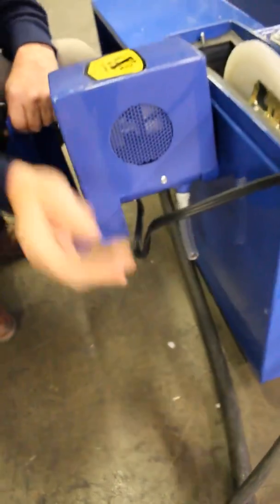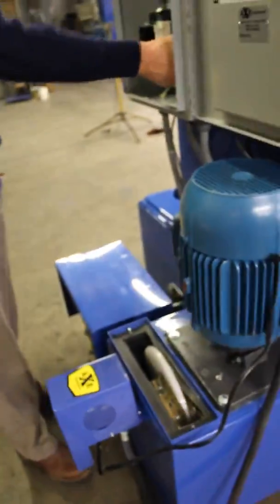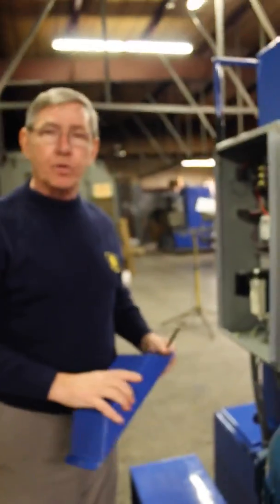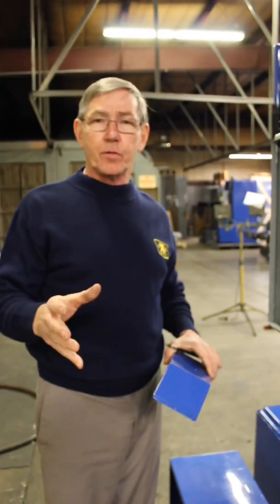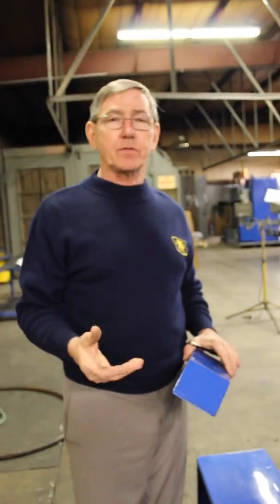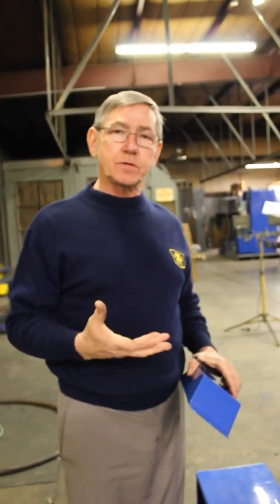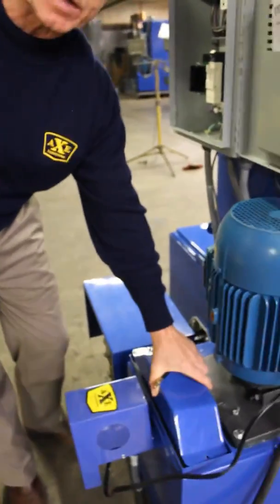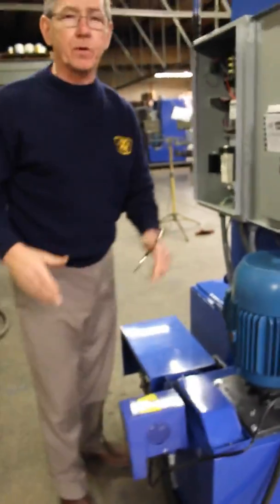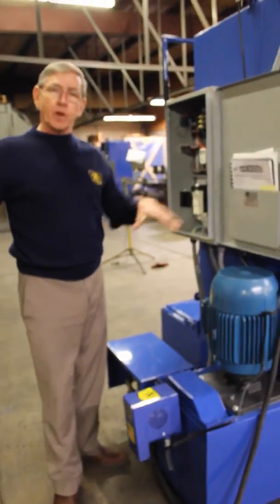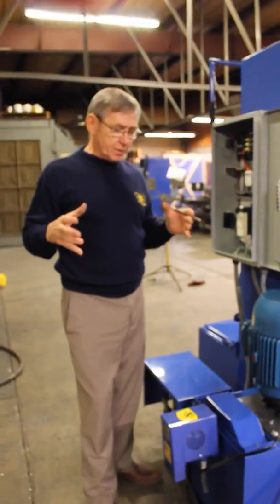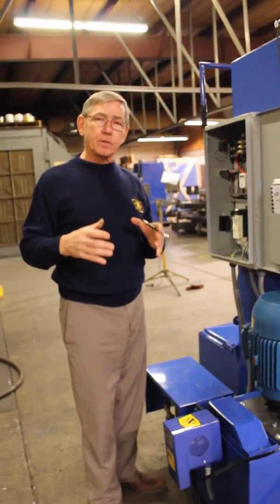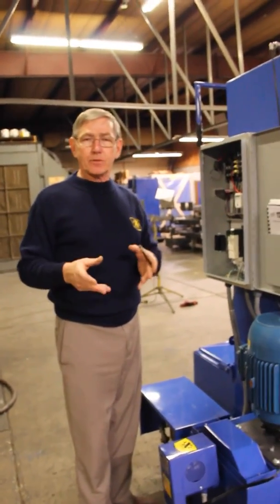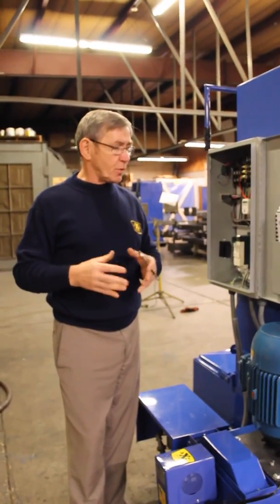You're gonna want to put a bucket under here. I don't have one here now, but you'll need a bucket to put underneath there. So anyway, the best time to skim your oil is when the water is cold. As you know, oil is lighter than water. So the time to skim is like 3 in the morning when all the oil has come to the top. So it needs to be, the colder the better. If you try to skim when it's hot, it's not going to do you any good, because the chemicals are keeping all the oil emulsified or broken up. So time it to come on early in the morning for about 2 hours daily, and do it when the water's cold.